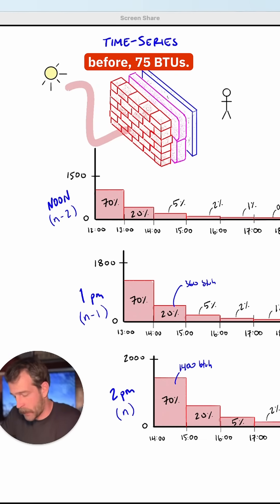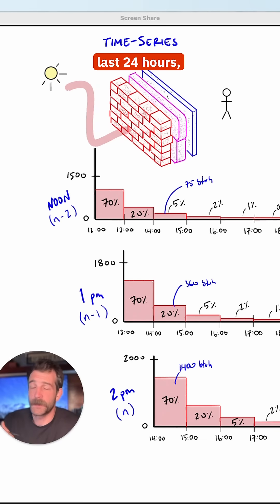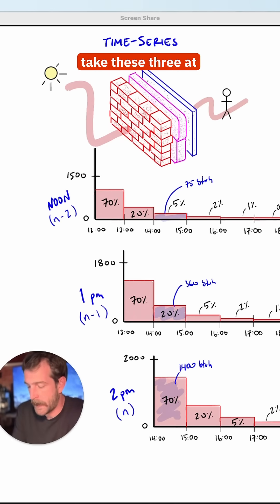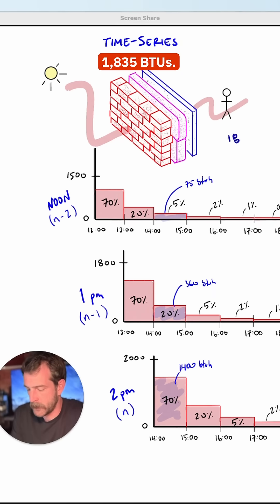And then likewise for the hour before, 75 BTUs. And imagine I did this for the last 24 hours, figuring out the load at that time, and then plotting the time series to see how much is entering my space. If I just take these three at 2 p.m., I'm looking at 1,835 BTUs.